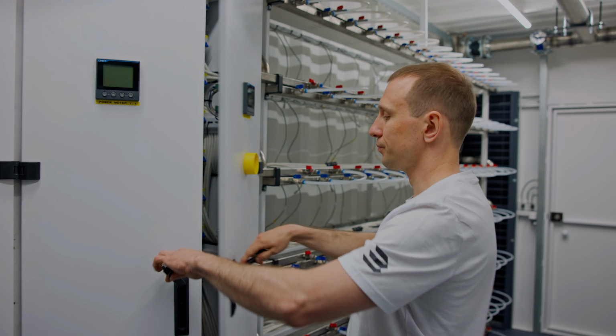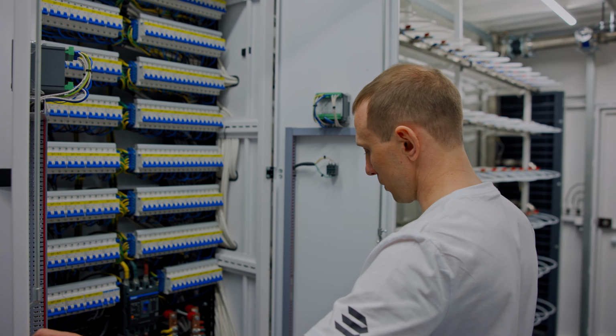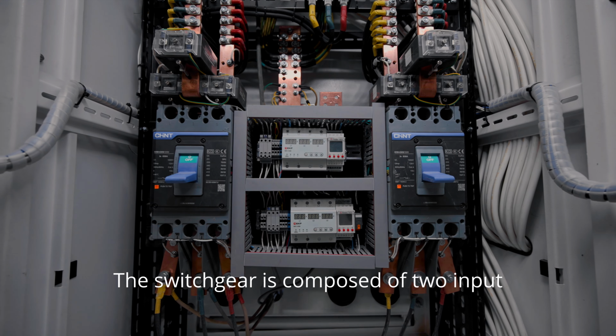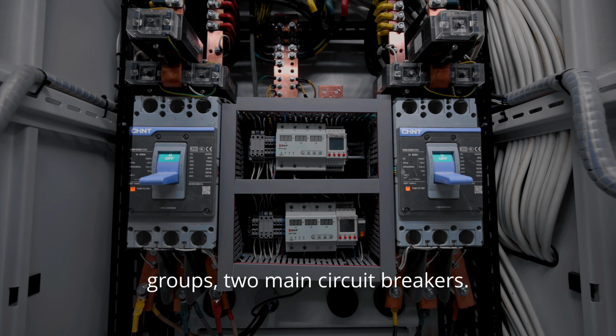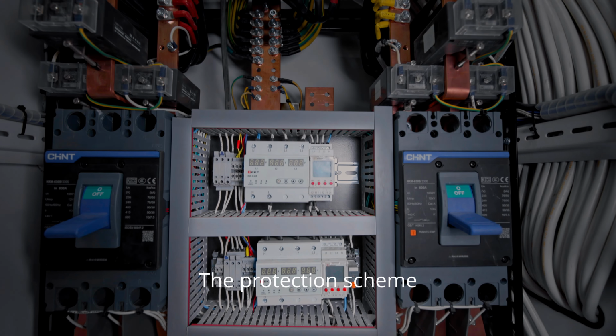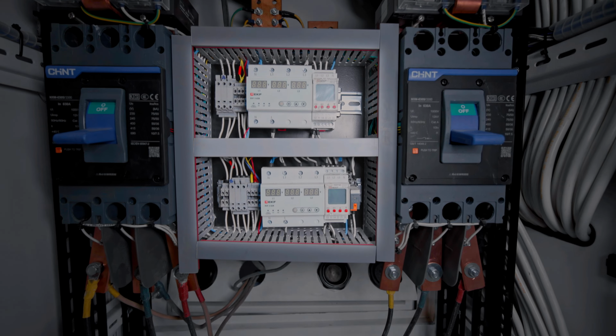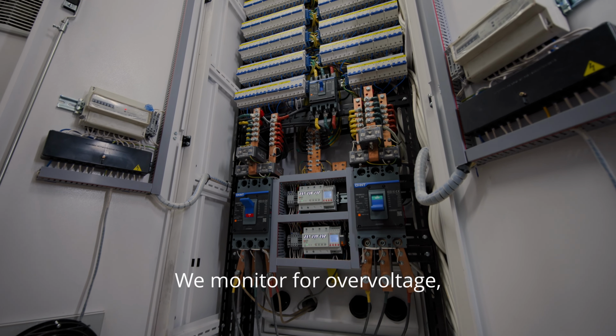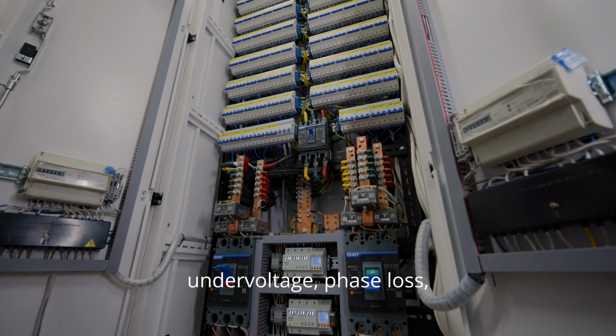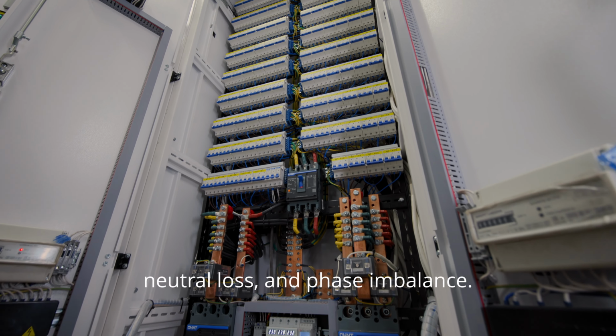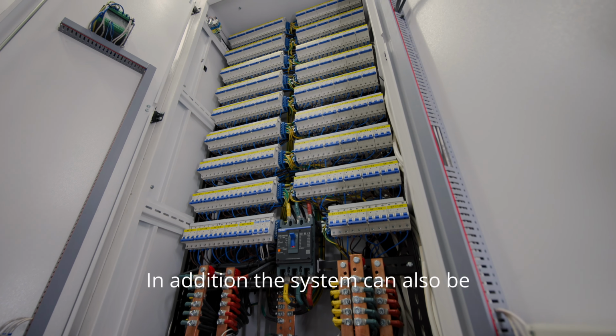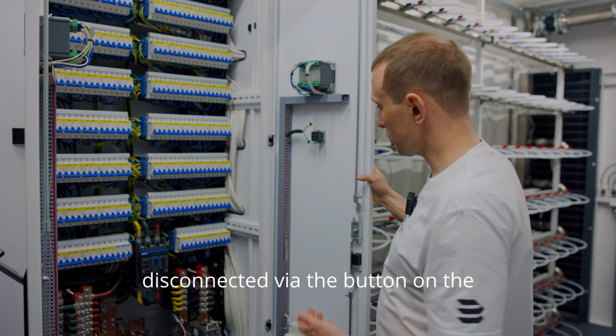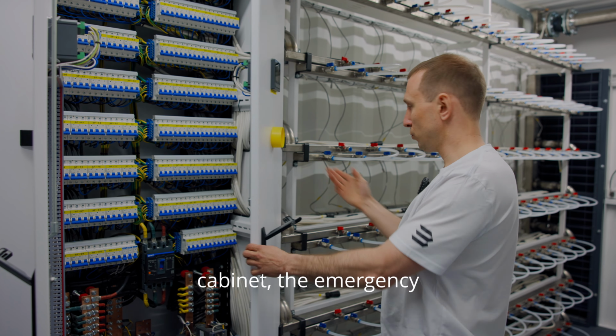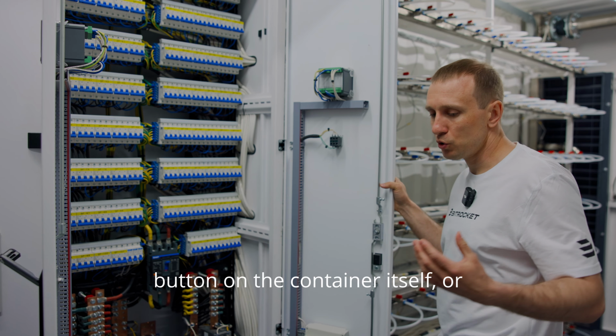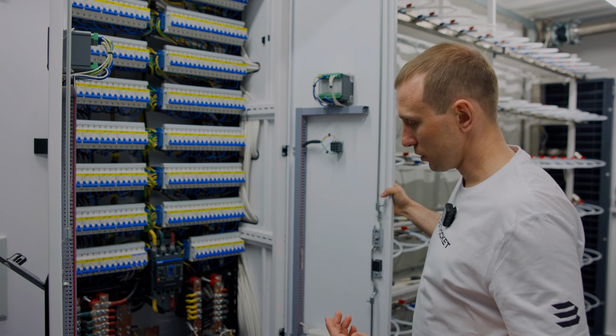Next, the switchgear is composed of 2 input groups, 2 main circuit breakers. The protection scheme uses independent trip units. We monitor for overvoltage, undervoltage, phase loss, neutral loss, and phase imbalance. In addition, the system can also be disconnected via the button on the cabinet, the emergency button on the container itself, or remotely through the controller.